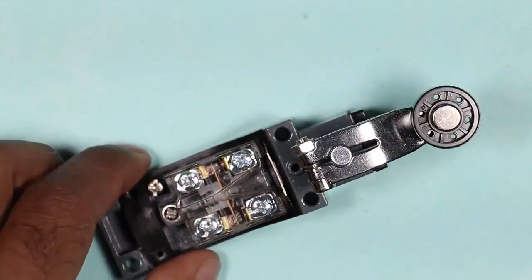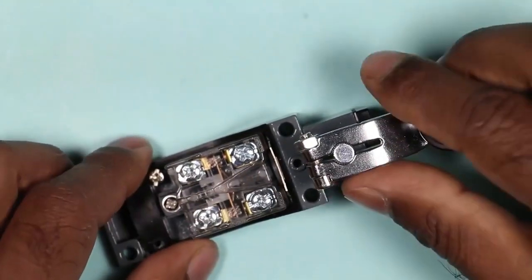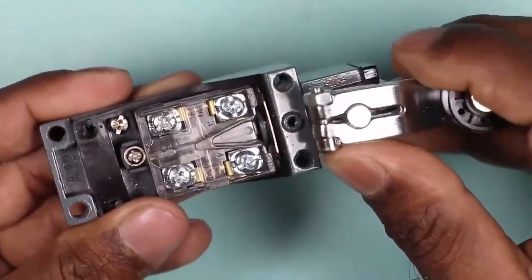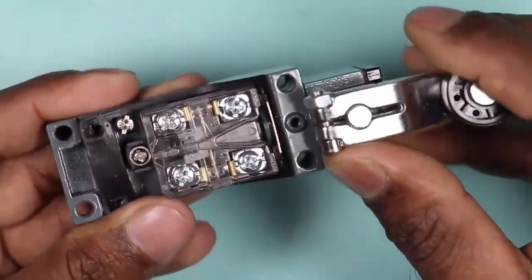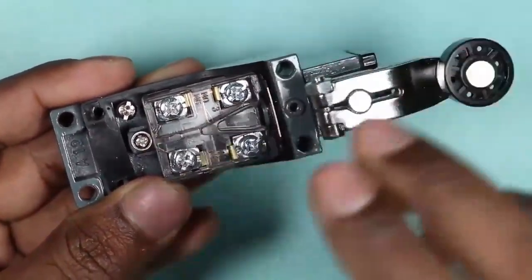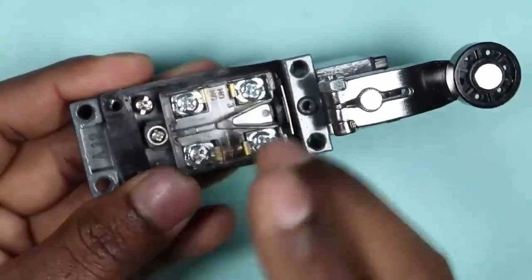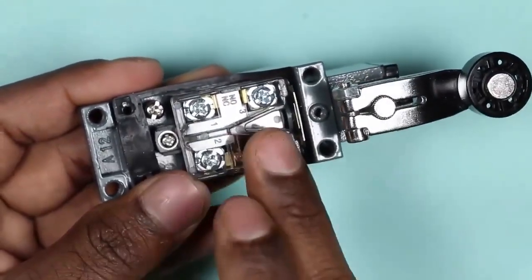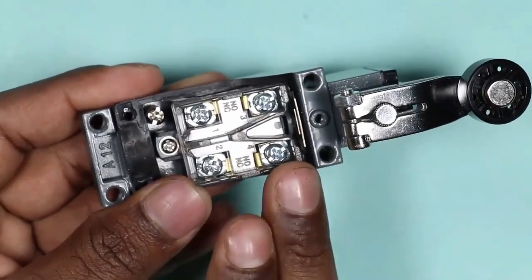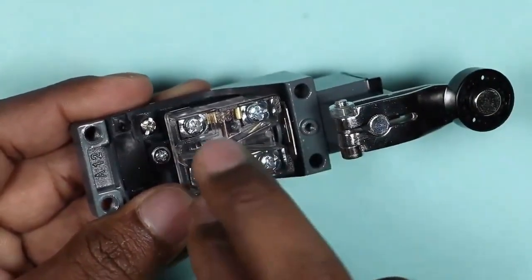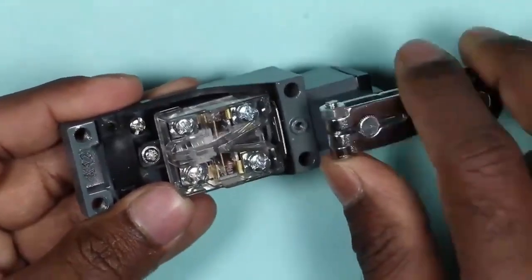of the plunger. To check whether the limit switch is working properly, just move the plunger and you will hear a knocking sound. You heard just now the knock knock sound. So if you move the plunger and a knocking sound occurs, then your limit switch is okay. But we cannot say this with 100% surety. To make sure this switch is 100% okay, you can use a multimeter and check the continuity here by moving the plunger. If NO-NC contact changes, then the limit switch is okay.